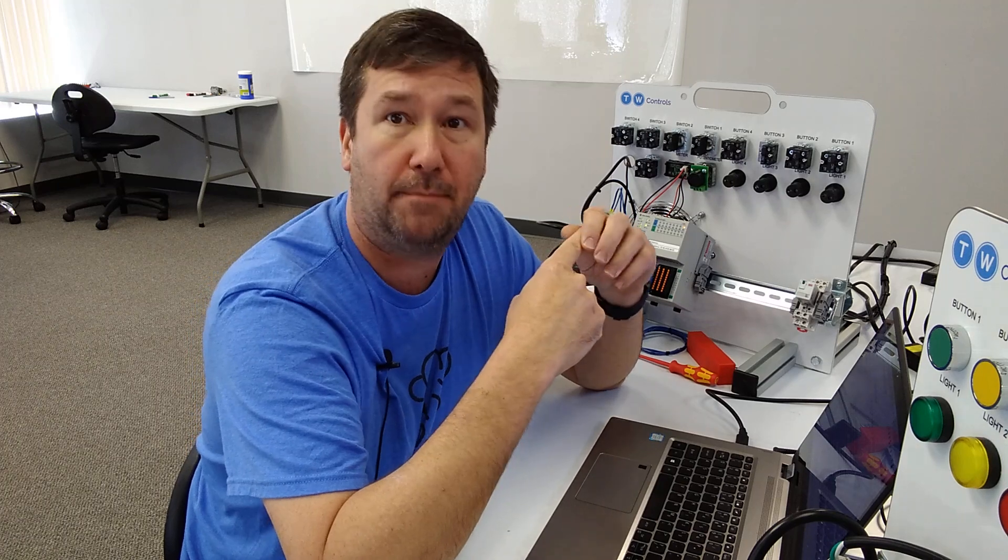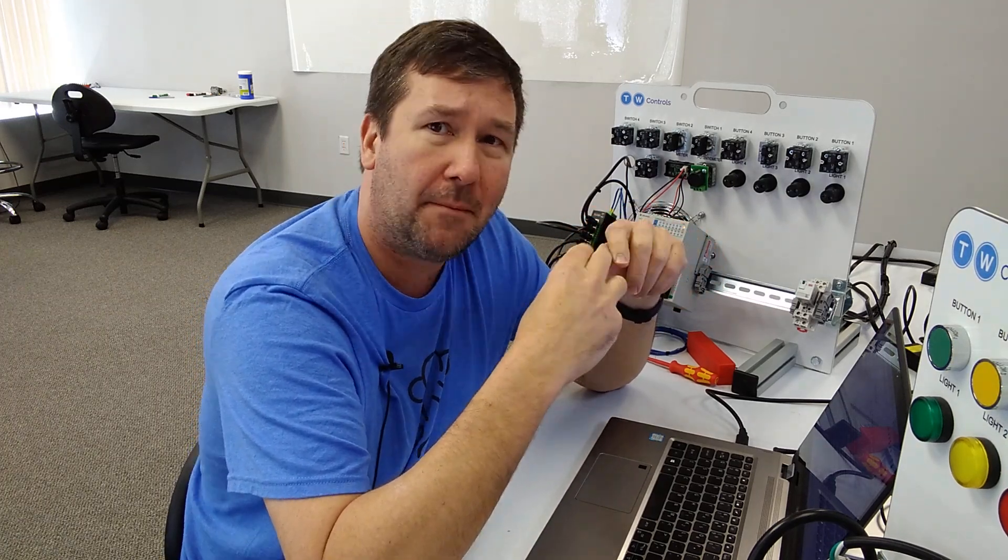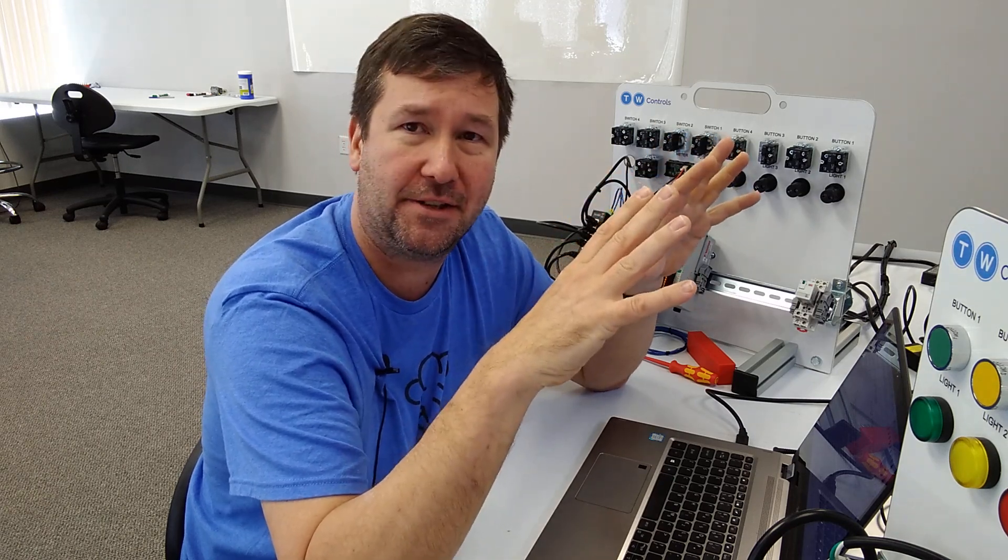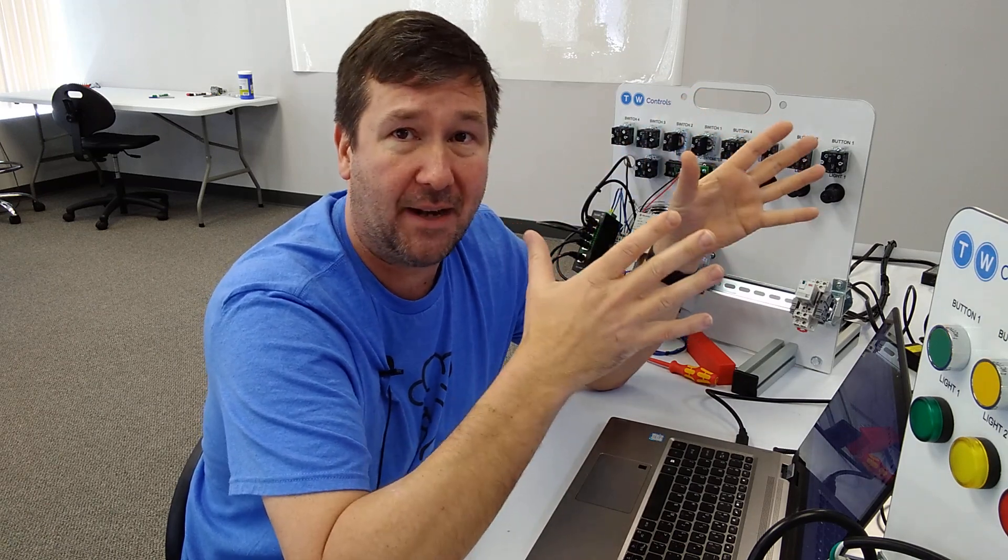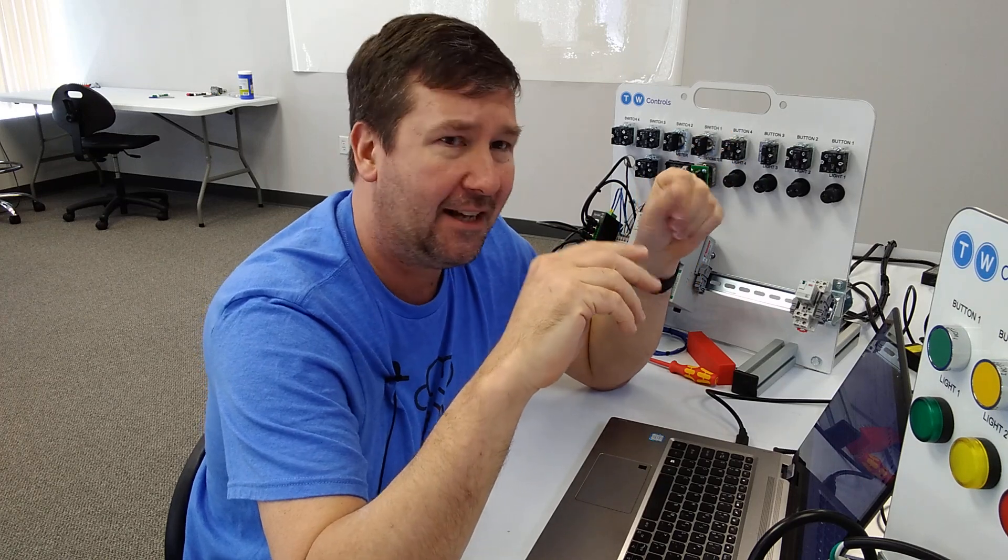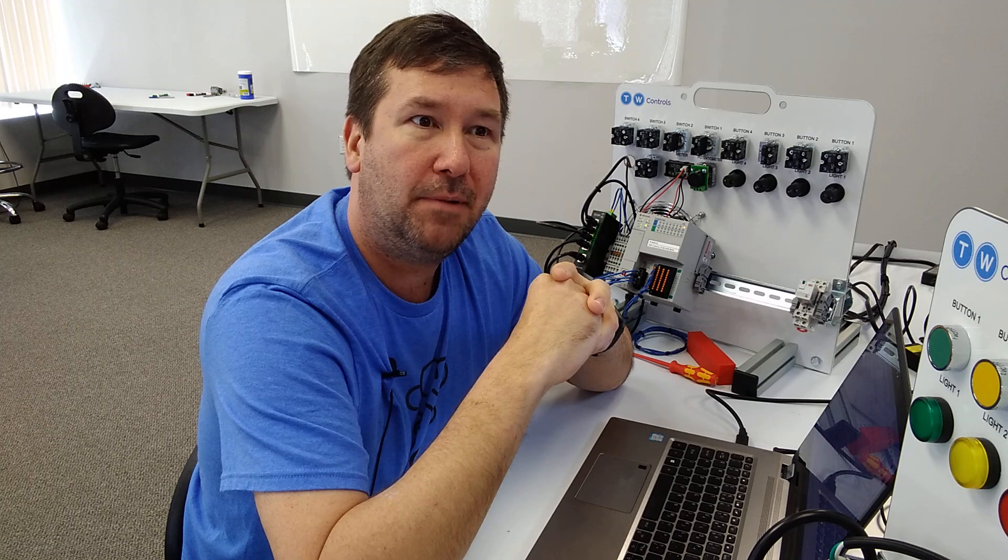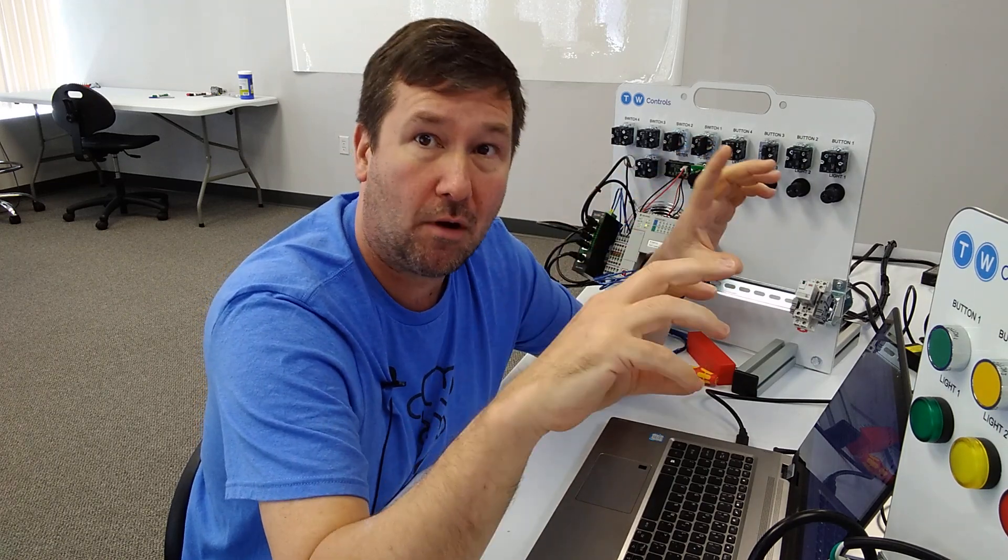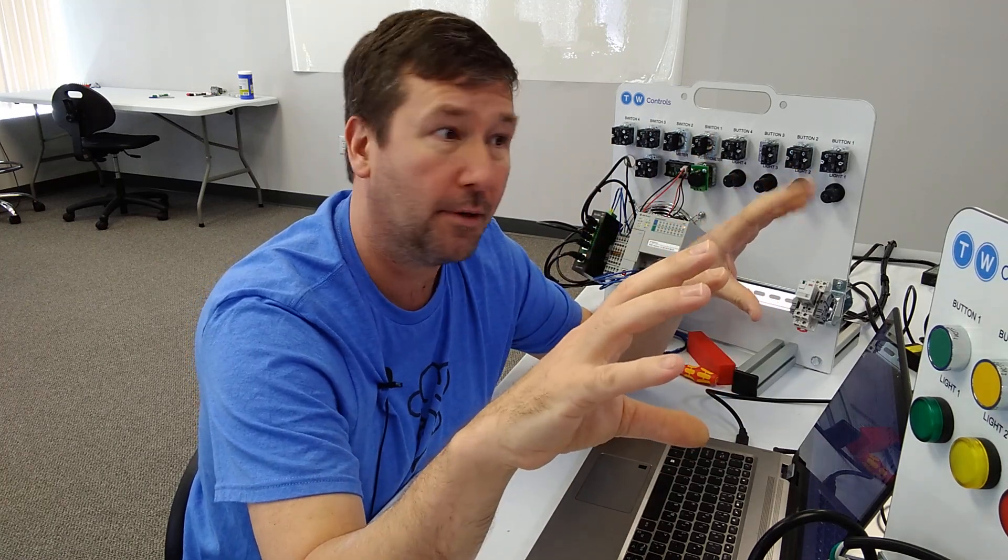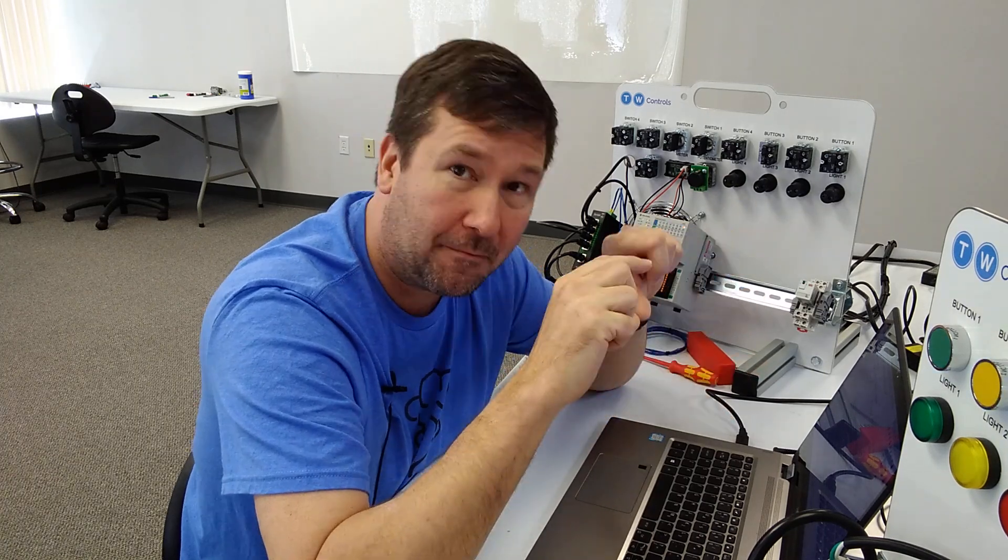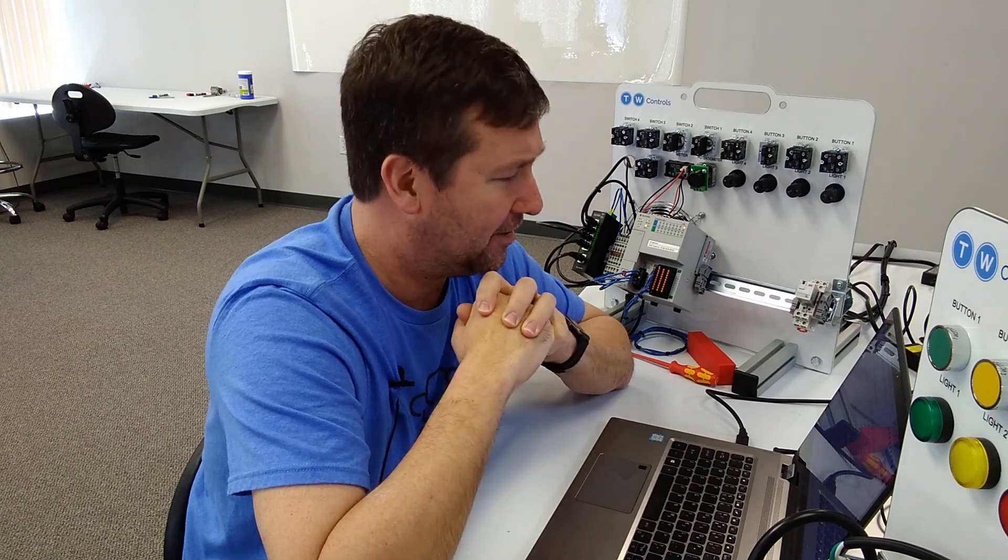This is really interesting. We do have a few about wiring doors, also about lining up disconnects through doors, but we don't have one about layouts. And that may happen with this HMI series we're doing, because we've had several people ask about layouts of HMIs and external buttons that may be associated with them. And also, it's really fascinating the people that get connecting wires to doors wrong, because it's a little shocking what you actually can and can't do to make your wires look really neat on a door. Probably the one that will upset a lot of people is you cannot take typical sticky tape and put wire duct on the door. It makes for a really beautiful installation, but there are issues with it on UL.